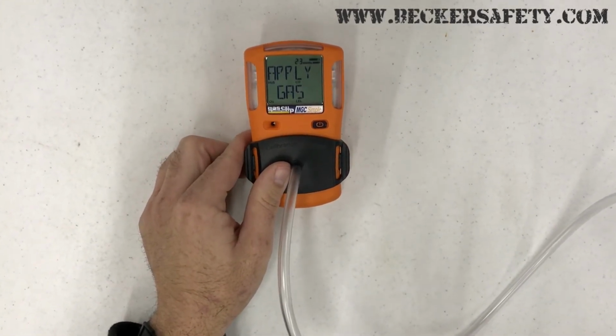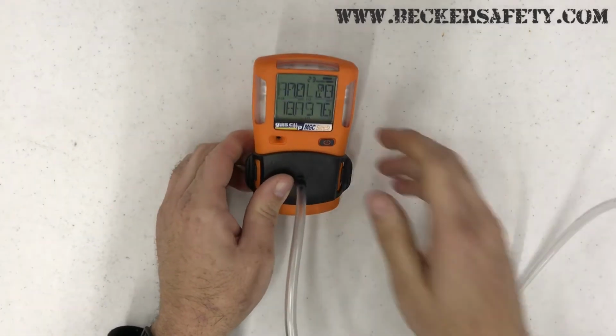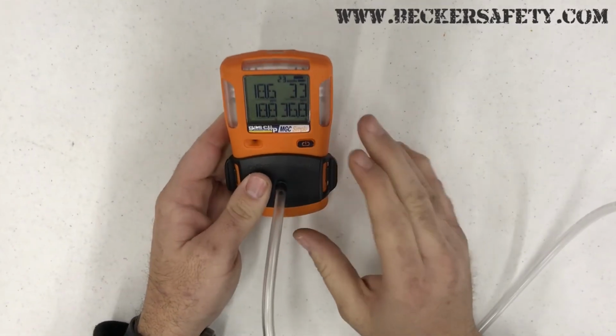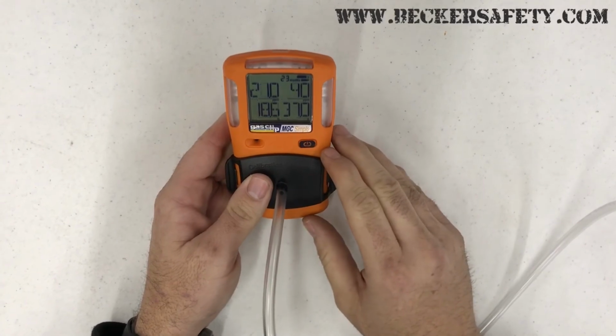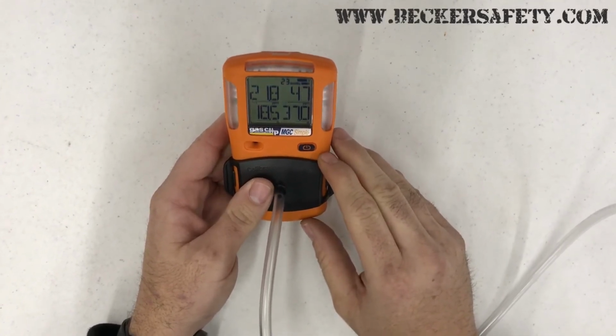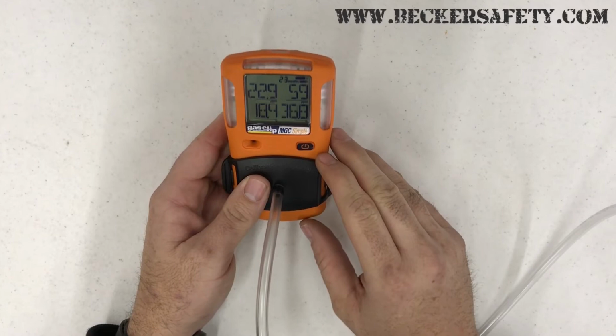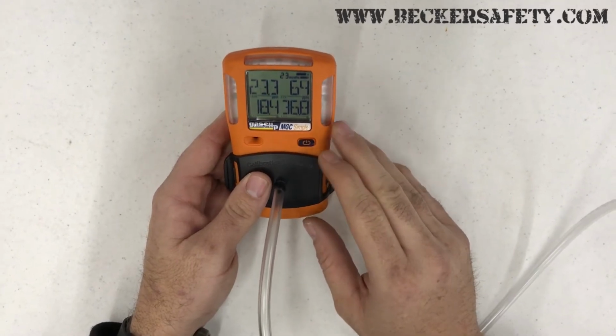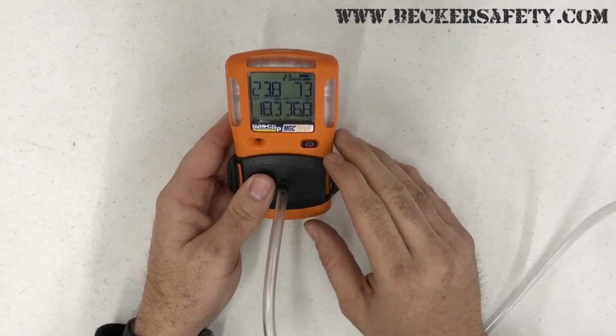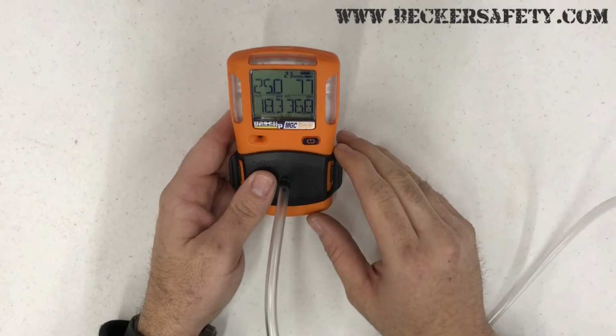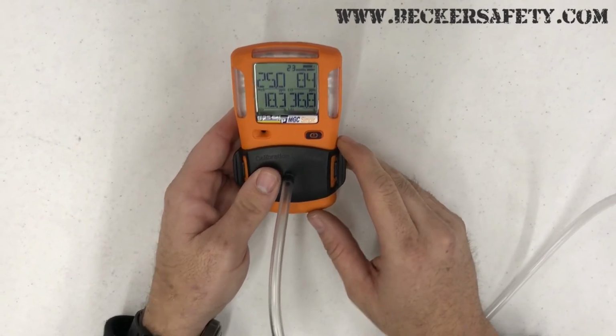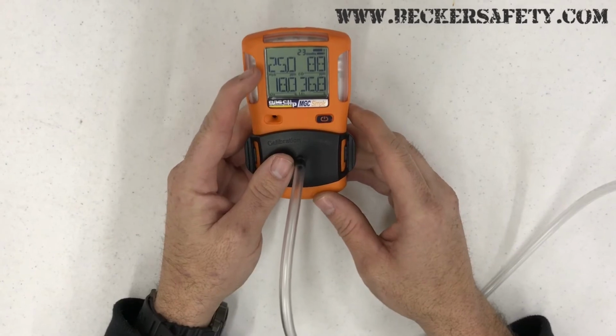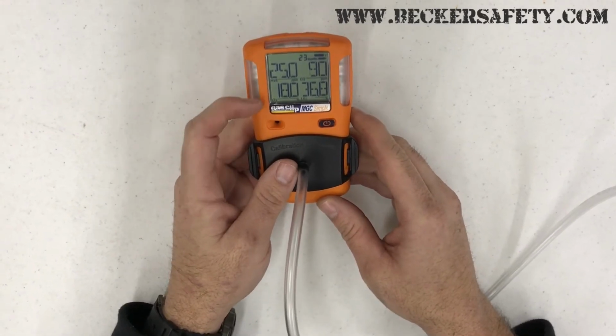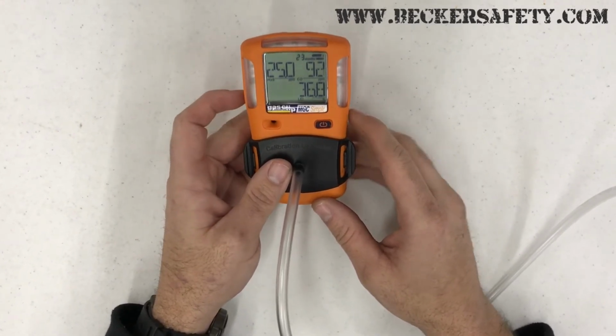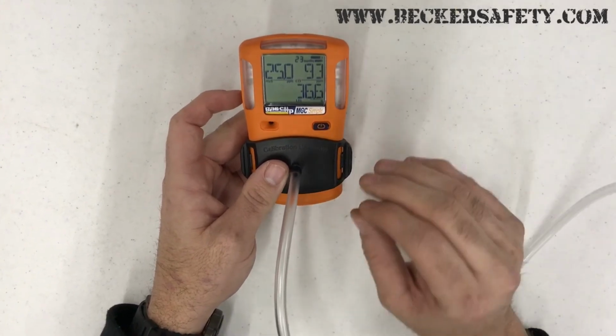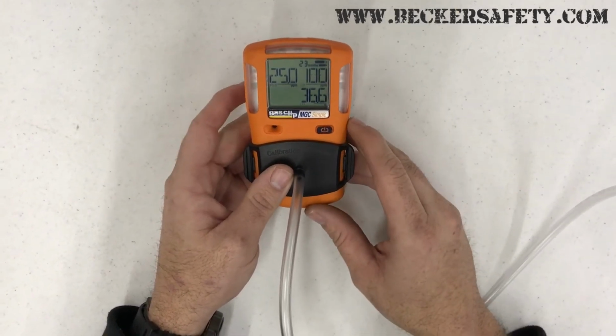The difference between a span calibration and a bump calibration, or a bump test: a bump test just passes the gas over the monitor to make sure that the alarm is alarming and the sensors are working. A span calibration spans the sensors, their whole range from lowest to highest. As you can see, they'll get to a certain point that they're set at, 25, 18, and once they steady out there, that is when you know that it's complete.